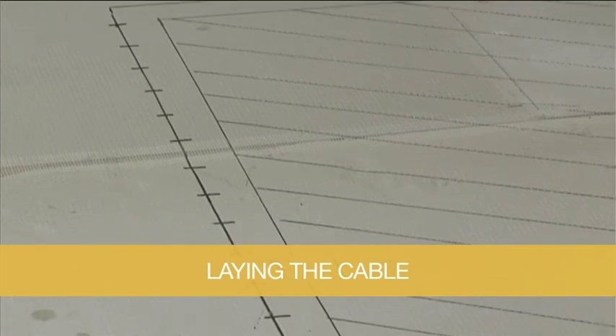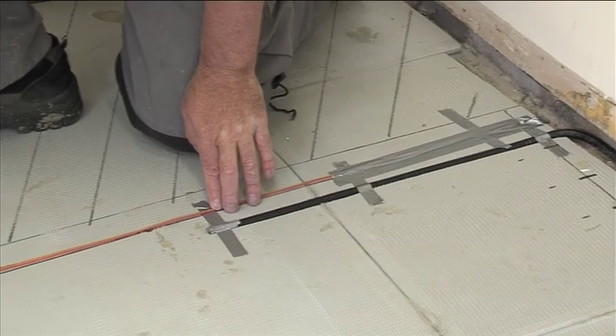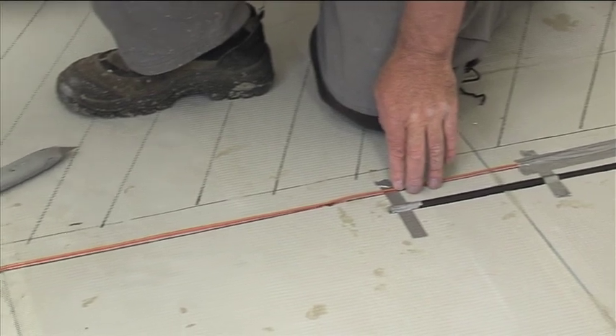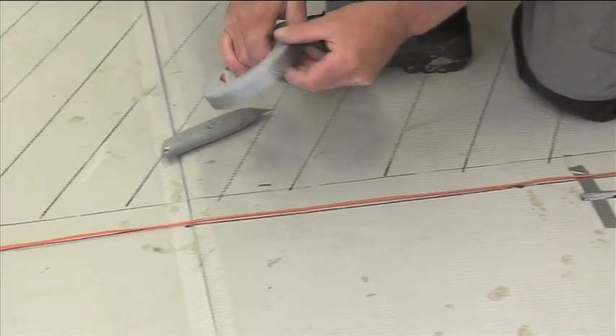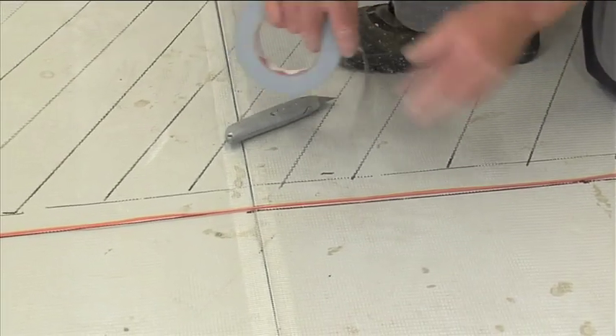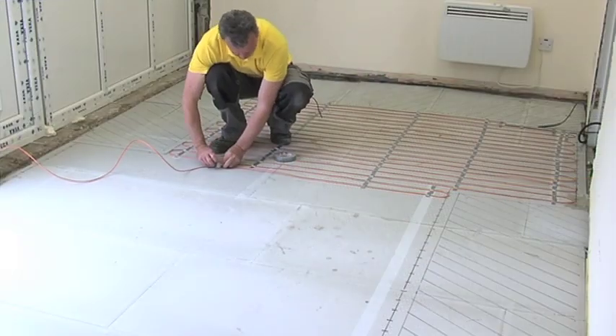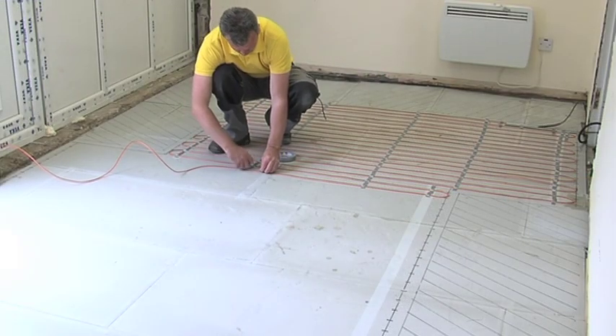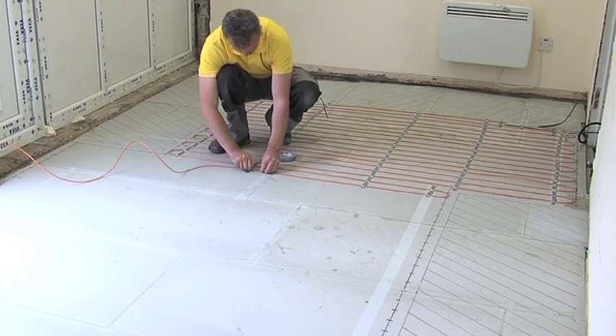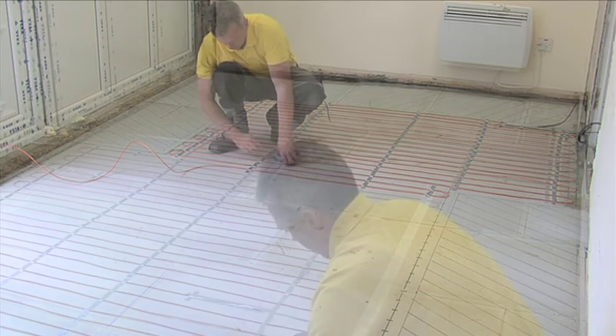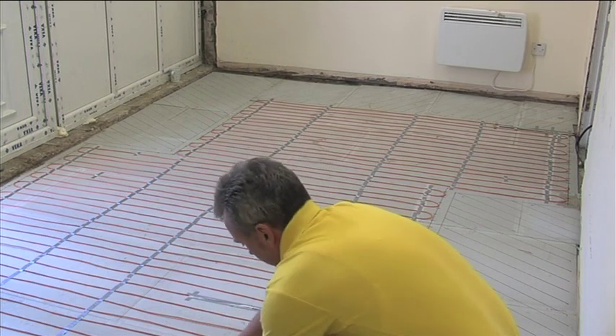Once satisfied with your marked up laying pattern, unroll the cable and lay in parallel loops using your pre-marked floor plan as a guide. Secure the cable to the floor using short strips of the adhesive tape supplied. At this point, only use a minimal amount of fixing tape, as you may wish to reposition the cable loops once the whole cable has been unrolled to achieve the best fit for the room.